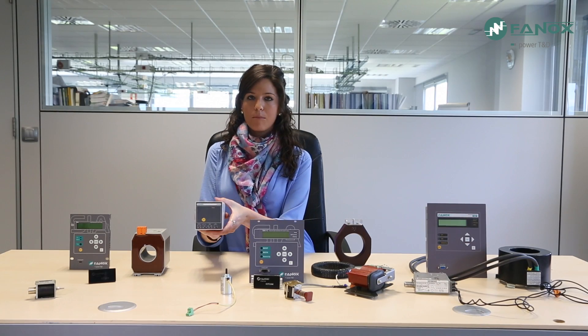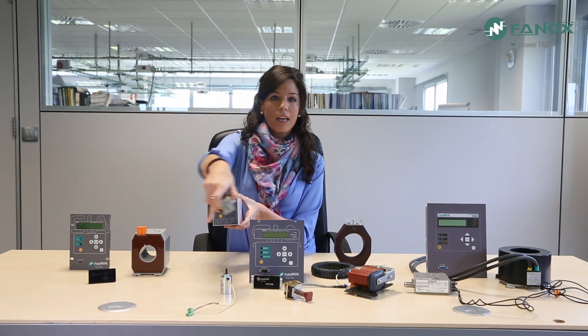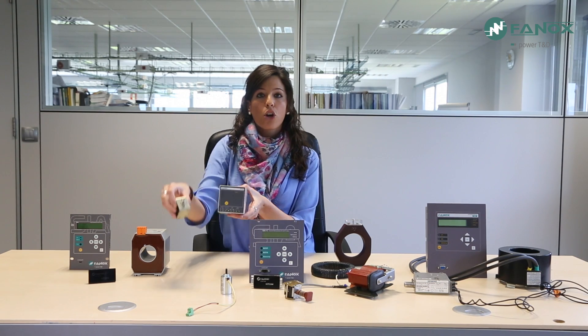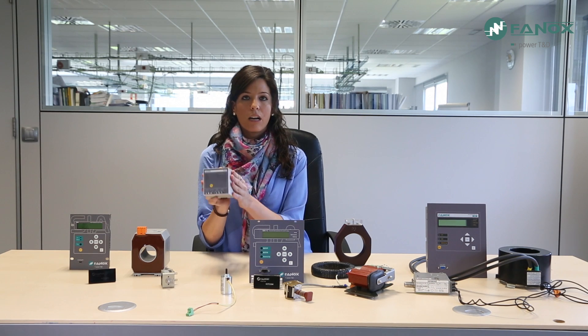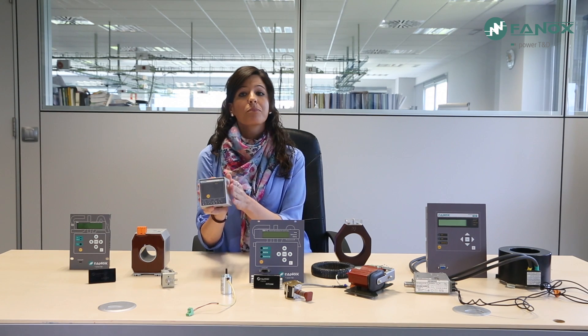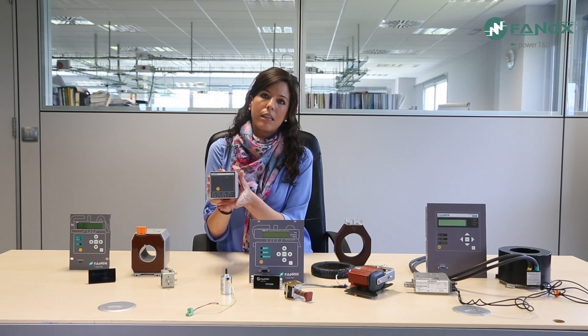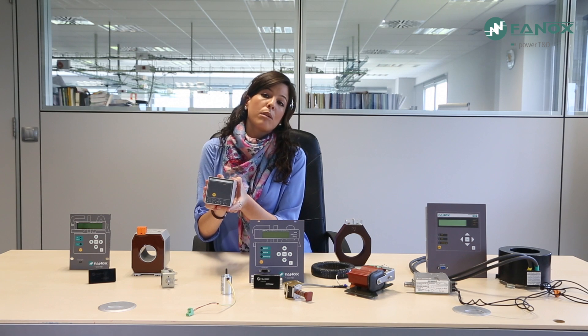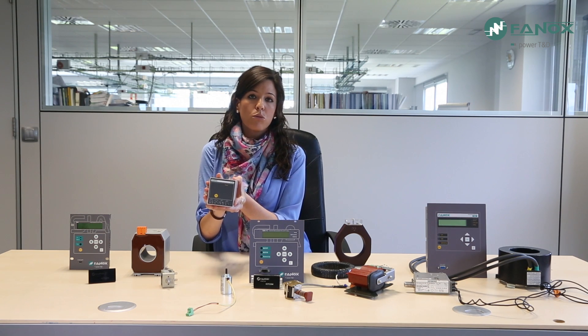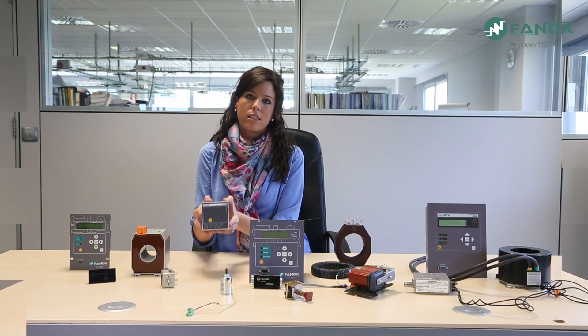Fanox offers the TCM adapter in its product catalog. The TCM is an energy accumulator used to trip the coil instead of the striker. It is a simple device connected to the trip contact of the relay. It can be charged before installation, or once installed if auxiliary supply is available. The charging time is approximately 10 seconds, and once power supply is lost, it has 3 days of autonomy.